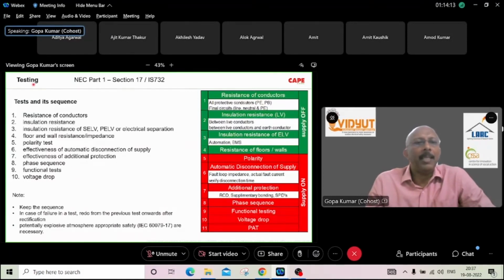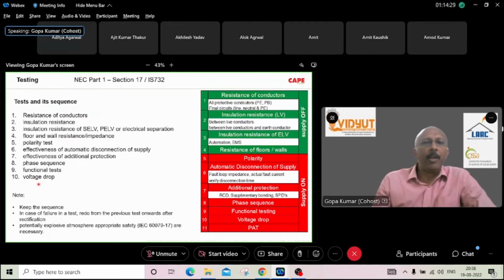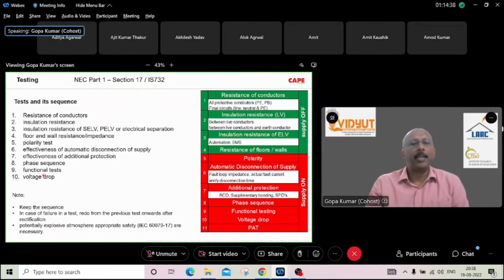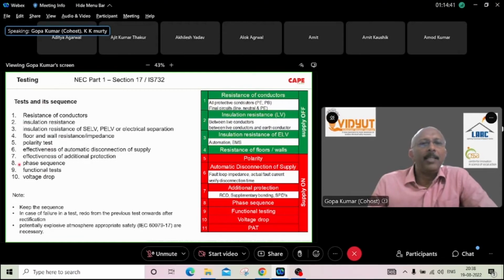The second part is testing. There are 10 tests included, not only in the Indian standard but worldwide. Of course, in Europe and some of the modern countries, they have added one more test, which is the 11th test called PAT, Portable Appliance Test. For a low voltage electrical installation, please understand that the majority of the accidents and fires happen from low voltage electrical installations. And these tests are mandatory, and this has been included since 1989. As I said, out of these 10 tests, 4 tests are carried out in supply off condition and 5 tests are carried out in supply on condition.